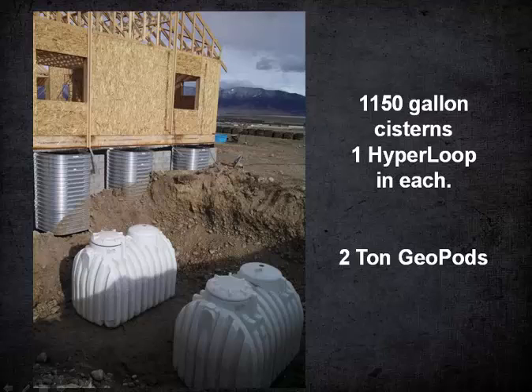Well, that works fine. They are available locally, and the Hyperloops were designed for pond applications, but they work great for going into these tanks because they just go right in the manhole cover, and then we build a PVC rack system that gets trapped into the corrugations on the tank that holds the Hyperloop up. So it's just in this kind of snail uncoiled formation in each of them. It's a real painless, easy process, a lot better than trying to wrestle a 700-foot loop of pipe through the manhole cover. That's a pretty ungraceful, sweaty process, and we've done it, but this is much, much easier.